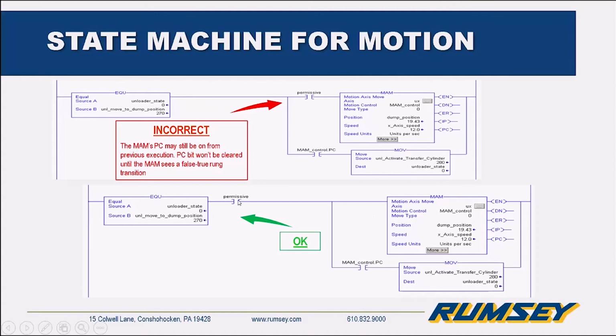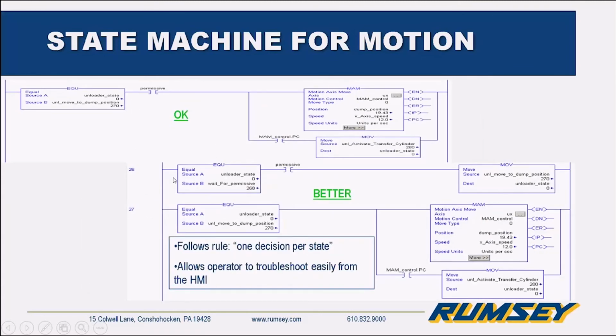It's okay, or better, to put the permissive out for the entire action and reaction portion of the instruction. Here we see the same repeat of what's okay, but even better might be to keep it, as I said earlier in the presentation, one state, one action, following the same one decision per state rule. Put the permissive in a state, then move on to the motion, so that it stays and waits in that state until whatever this permissive may be, the loader is full or something like that.